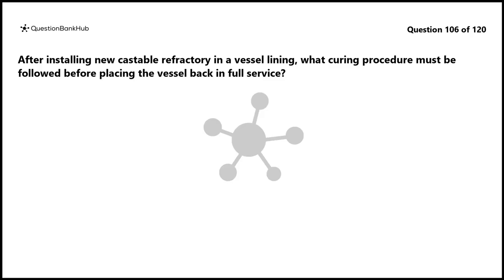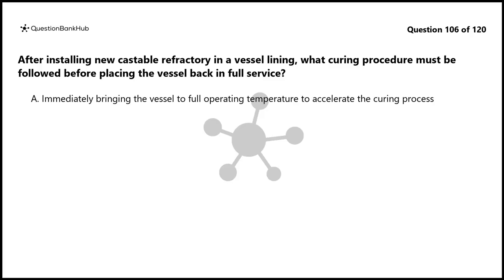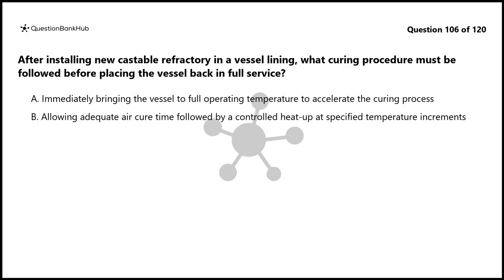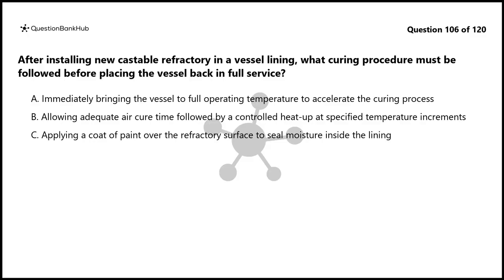Question 106. After installing new castable refractory in a vessel lining, what curing procedure must be followed before placing the vessel back in full service? A. Immediately bringing the vessel to full operating temperature to accelerate the curing process. B. Allowing adequate air cure time followed by a controlled heat-up at specified temperature increments. C. Applying a coat of paint over the refractory surface to seal moisture inside the lining. D. Allowing the refractory to air cure and then cooling it rapidly with water spray.